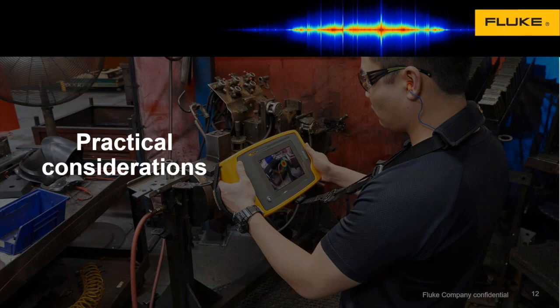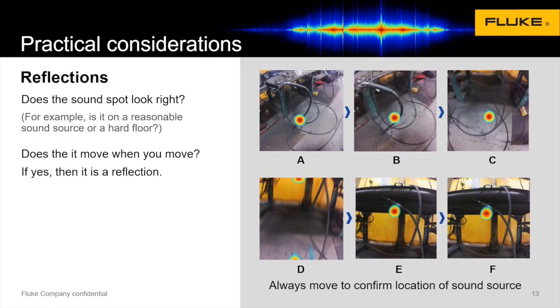Now let's get into some of the practical considerations to give you a feel for how this camera operates out in the factory or field. One thing you've got to be mindful of when using this device is reflections. What you're looking for when scanning for a leak is targets that show up on the screen and stay on the screen. If they pop in and out, those are just echoes or sound bouncing off different surfaces — they're not actually leaks. Unless you see a target that stays on the screen, it's likely a reflection.